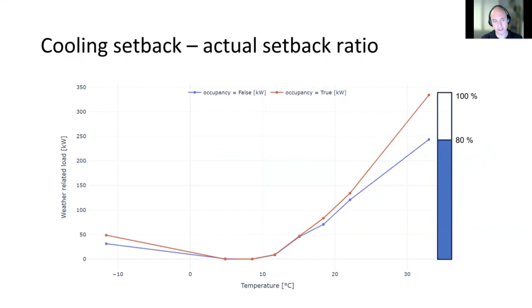You see that at the maximum, this 100%, it's related to something almost 350 kW, and during the unoccupied hours it goes to 80% of that. So we say that the cooling setback is something like 80%, and you may guess that this is not ideal, that during the weekend when the building is unoccupied, they do not need so much cooling, and it could be lower.